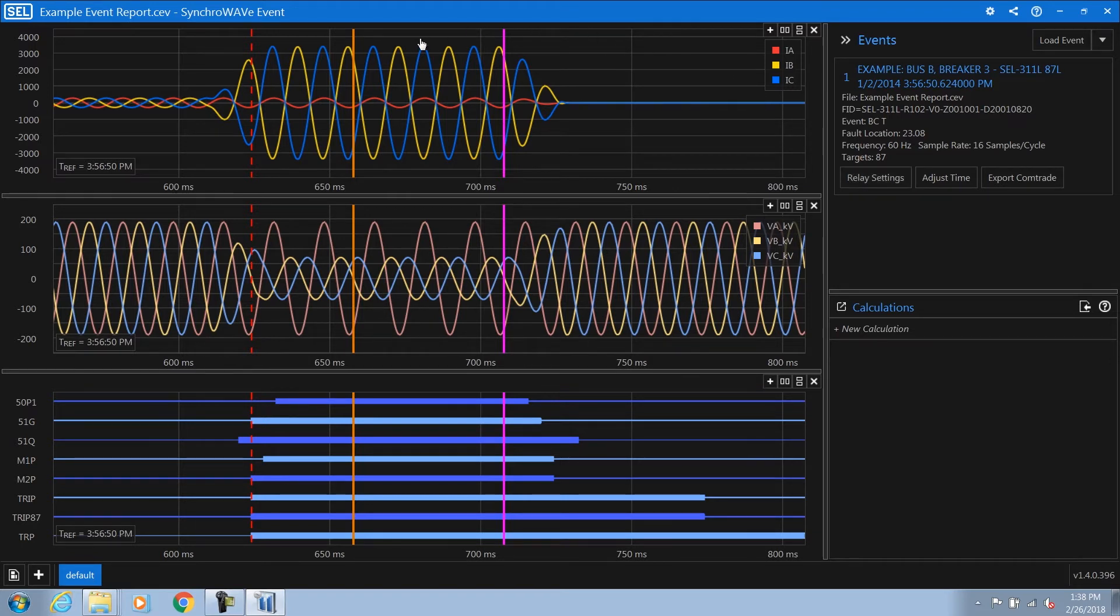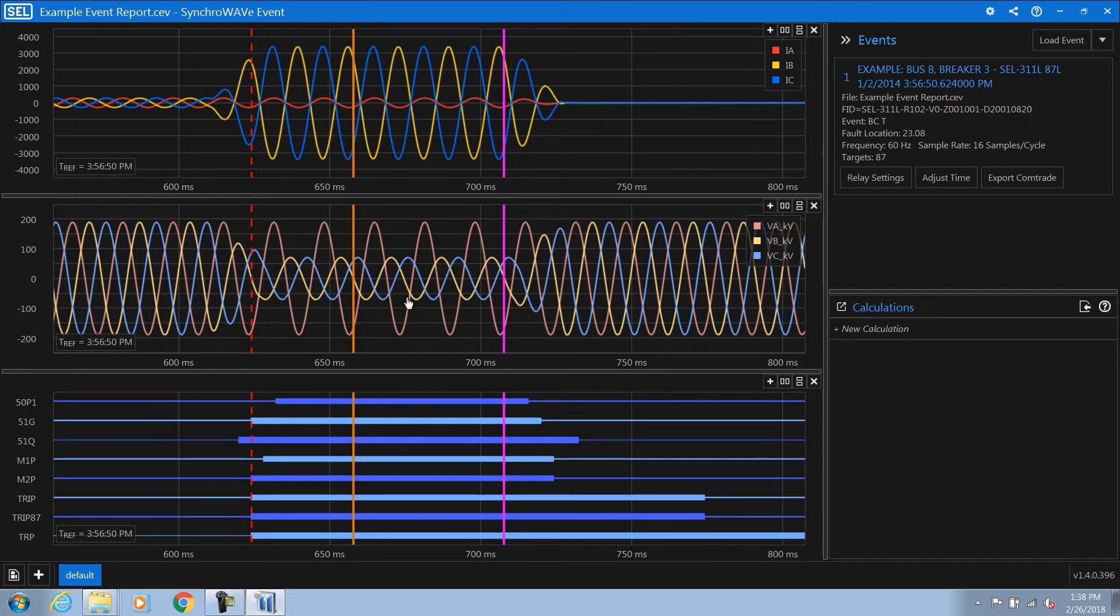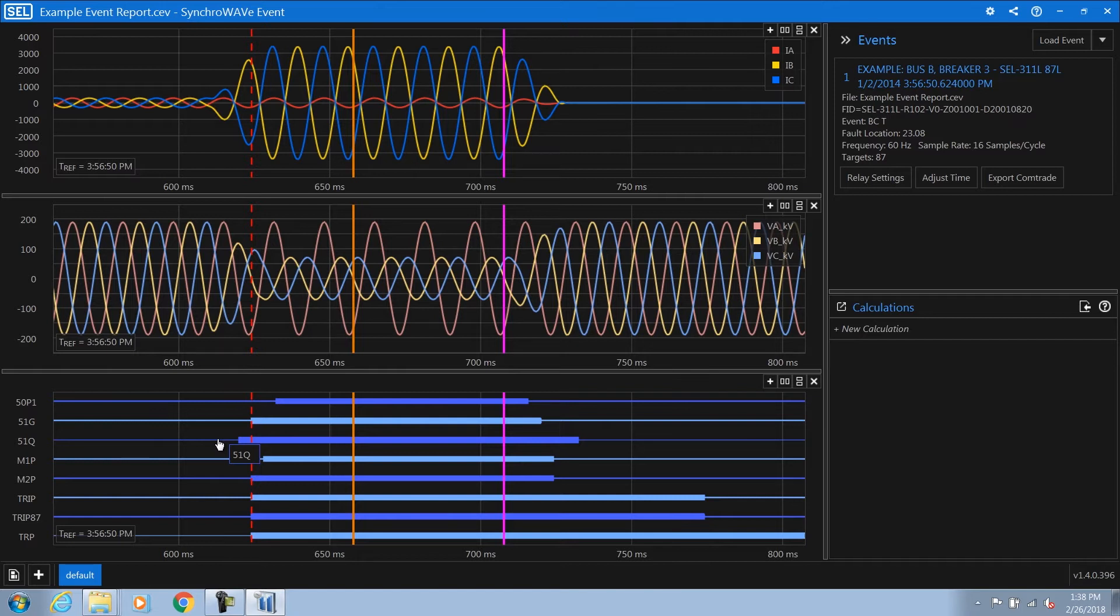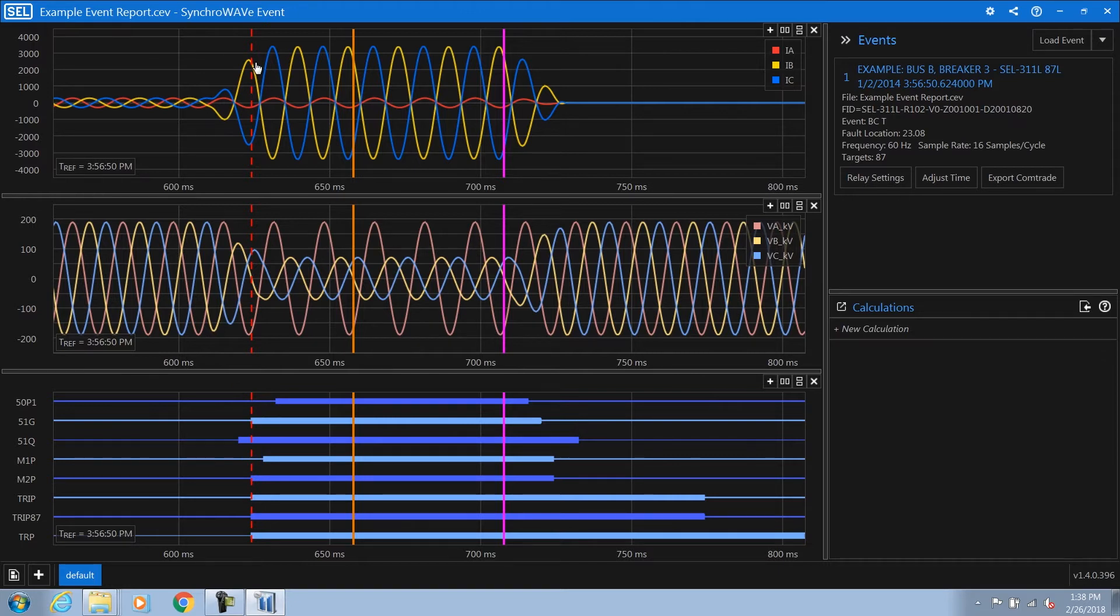On the left hand side we have our analysis workspace. The analysis workspace provides the current waveforms followed by the voltage waveforms and lastly the digital status. SynchroWAVe Event helps engineers more effectively analyze events by automatically looking at the relay settings and the trigger equation and detecting any digitals that asserted or changed state in the relay trigger equation and plots those automatically for the user in order to make analysis more efficient.